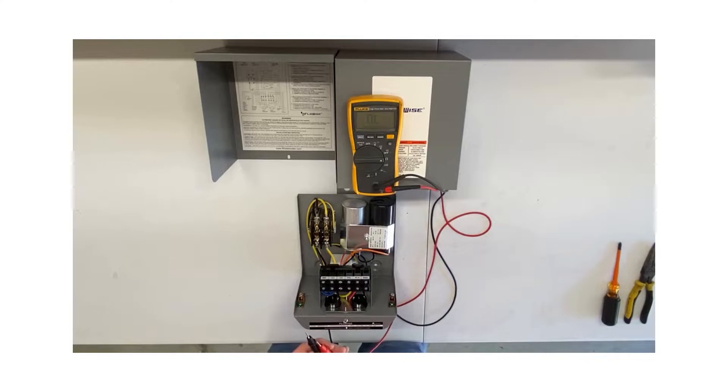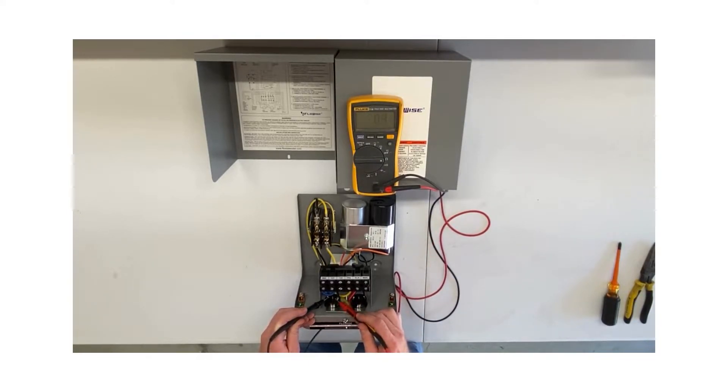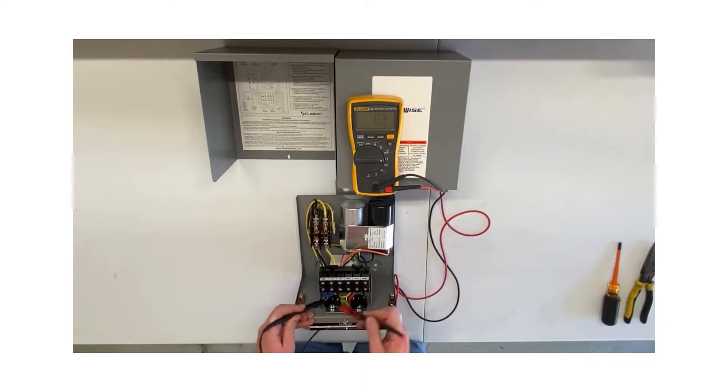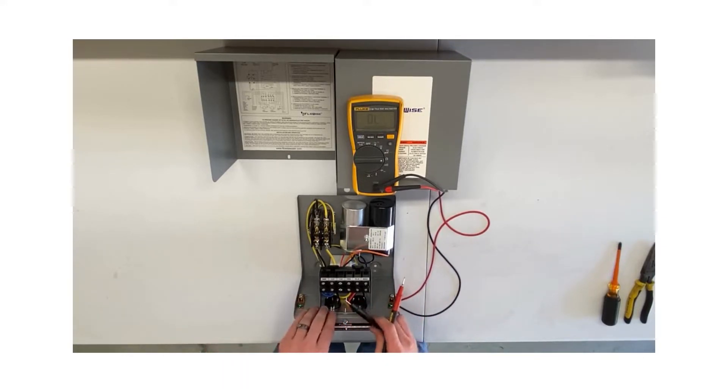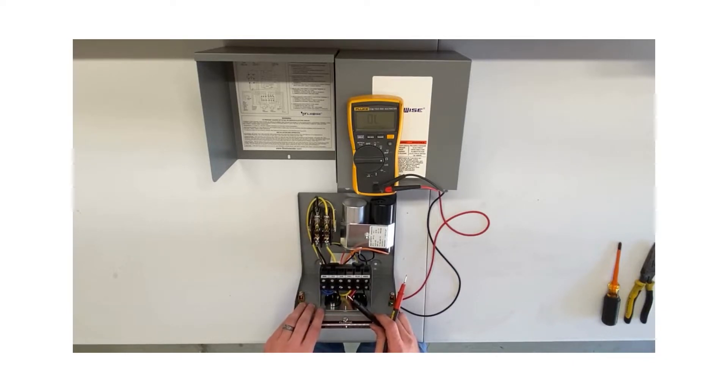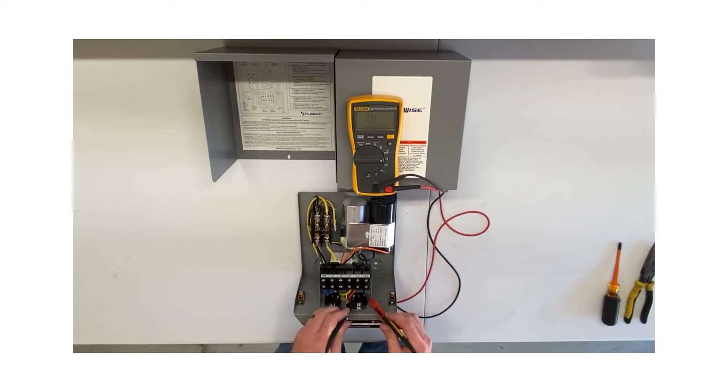I'm going to take one probe and touch it to one side of the overload and the other probe to the opposite side. I'm getting 0.3. My zero was 0.3, so when I subtract the two, I get zero. The manufacturer says for an overload to be good, the reading cannot be more than 0.5 ohms. We have zero ohms of resistance, which tells me this is good. Let's check the other one—0.3, so that one's good too.